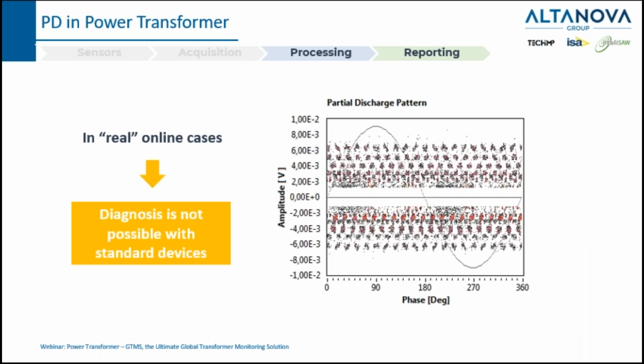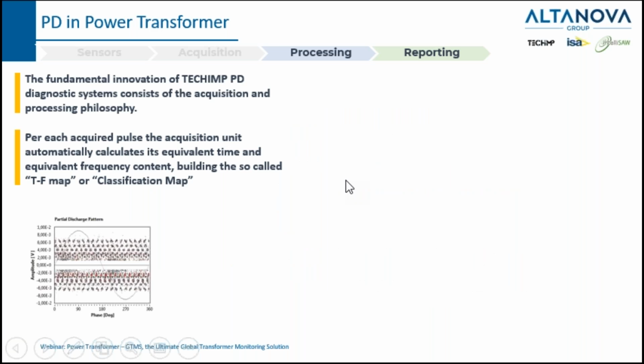In this other example, it's not really an example, it's a real case. We have to highlight that when we move from the laboratory to real cases, diagnosis is normally not so easy to achieve. It's not possible with standard devices. As you can see here on the graph, we have a high level of background noise, and in online tests and monitoring it can be very hard to get good results because of this very high level of background noise. We started more or less 20 years ago to develop a method to reject the noise in such conditions in order to identify partial discharge even in online assessment. This is our fundamental innovation of Techimp Altanova technology.